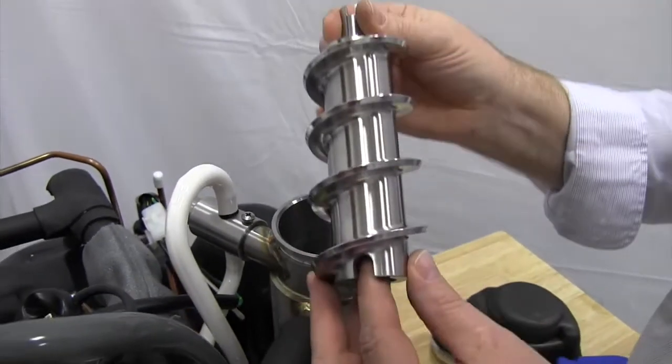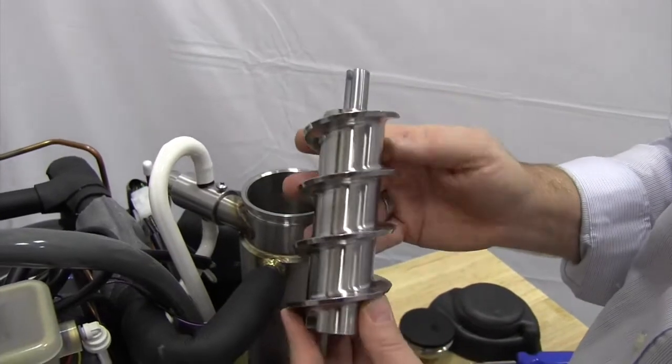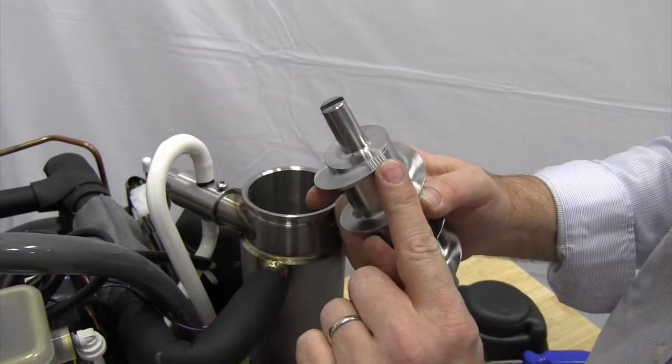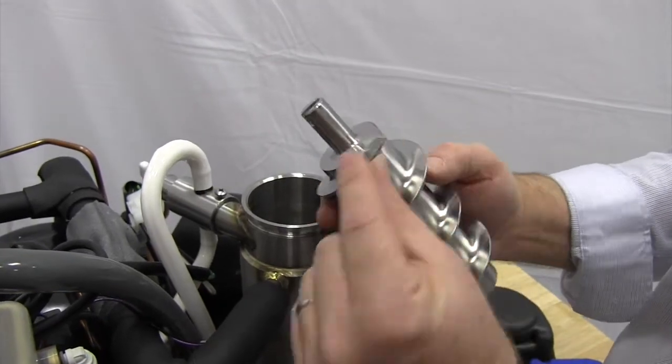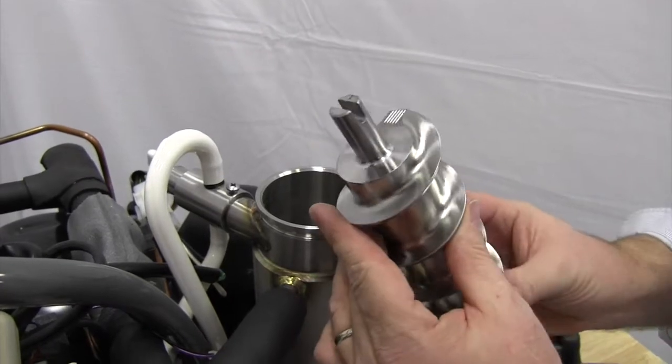So here's our auger. The auger is machined out of a single piece of 304 stainless steel. It has some little serrations up at the top here. What those serrations are for is it helps to give the ice a push, to push it out of the evaporator as it's turning around.